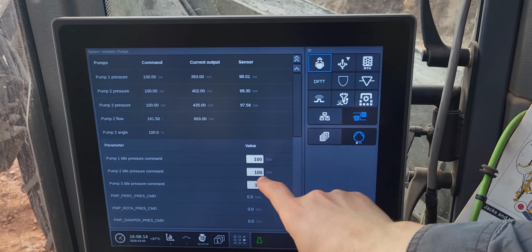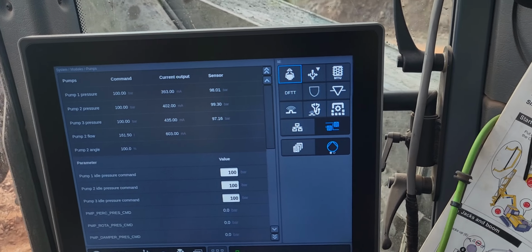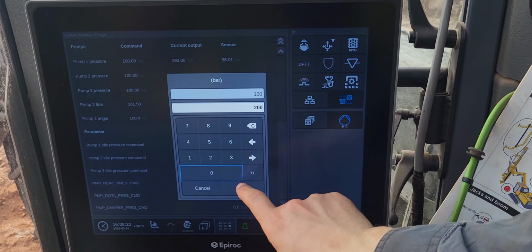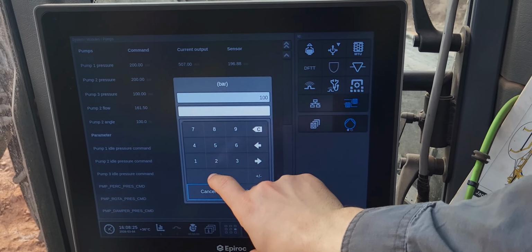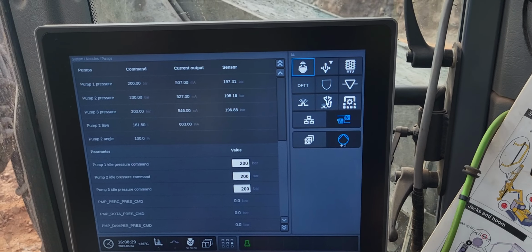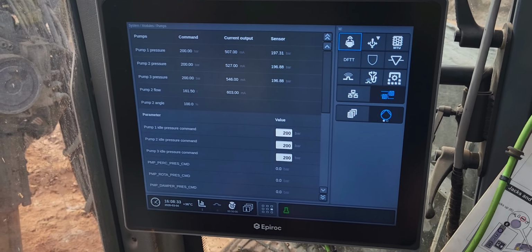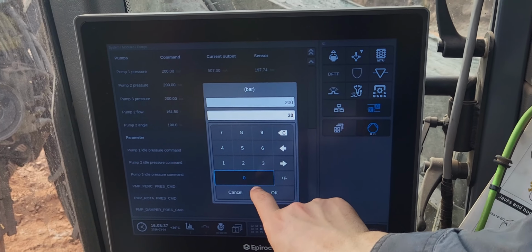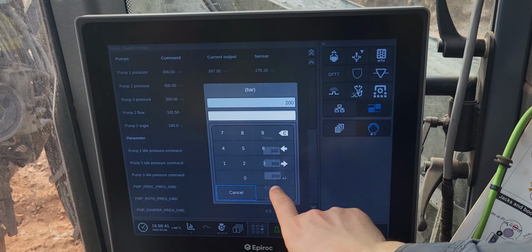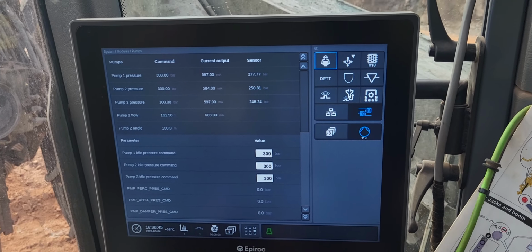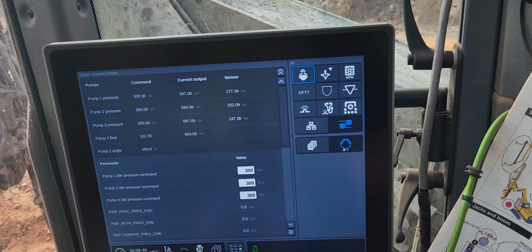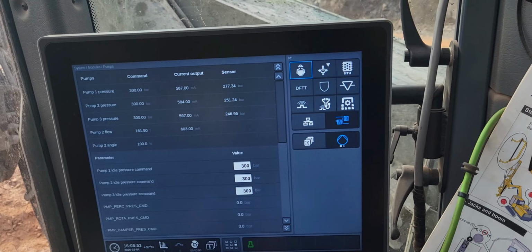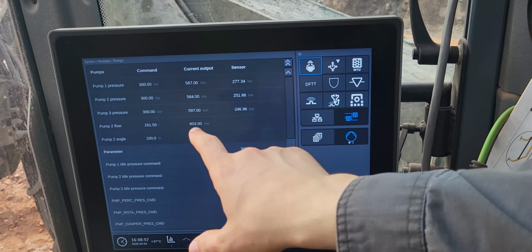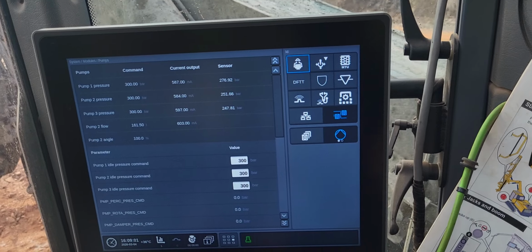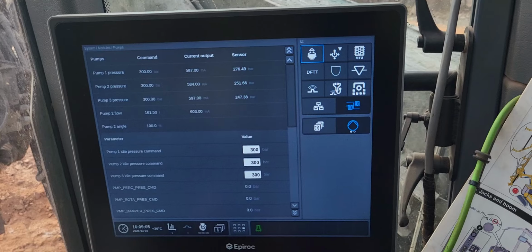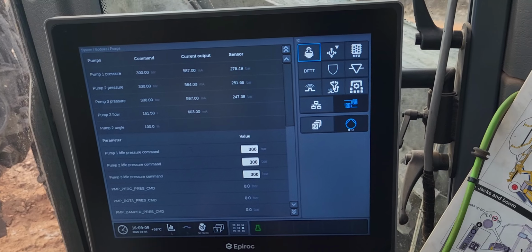So you can see I need to check always, so if I actuate 100 it should be around 100, then I can check like 200. Perfect. 507, 527, that's okay. And then we check for the maximum pressure. 300. So maximum pressure of pump 1, around 280, no more than 280. Let's say between 260 and 280 is okay. Pump 2, 250. Pump 3, 250. Plus minus 10 is better, like if it is 247, that's perfect. Below 250. Okay? Very good.